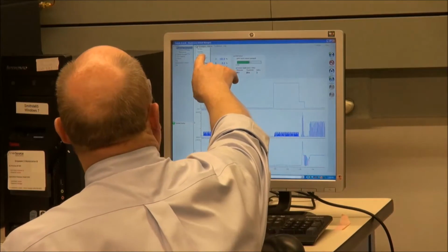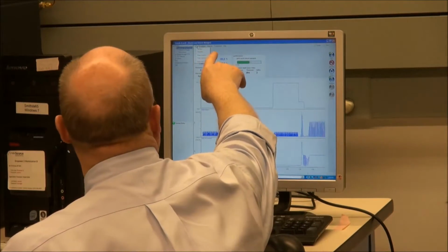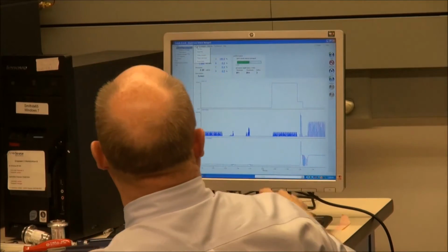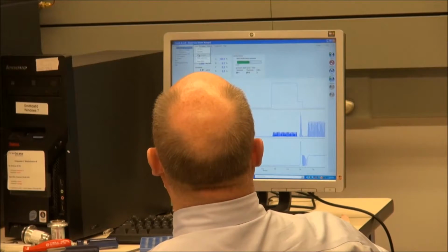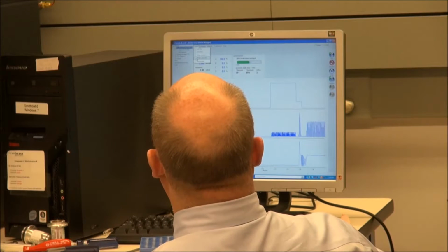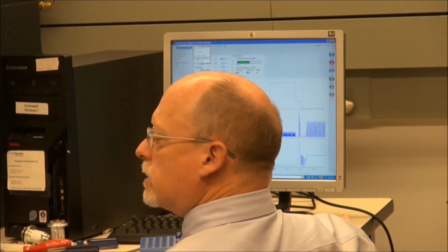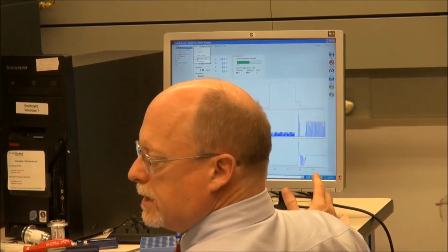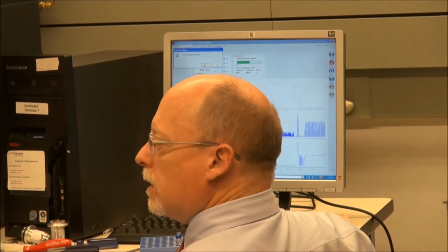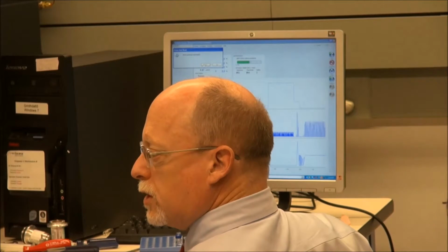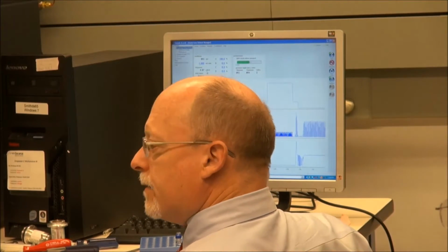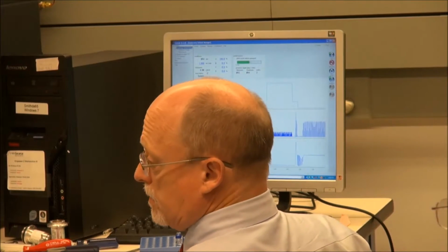Okay? So, how we can get in the service mode? Go to troubleshoot, service mode, and it'll open the window 1147. Okay, so I've got prime solvents, stock flow, set flow, prime seal wash. Okay, this is interesting. Now, I told you I was going to teach you how to listen for things. So if I prime seal wash, I want to listen for, see if I have one click or two. If I have 2 clicks, then I'm not primed.